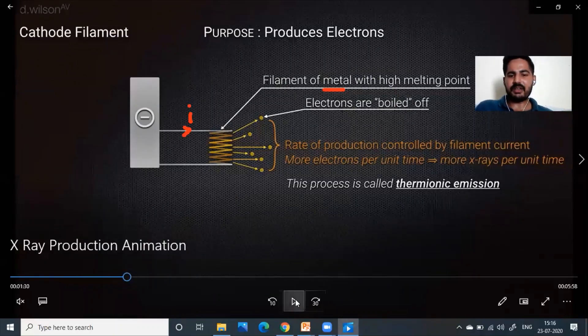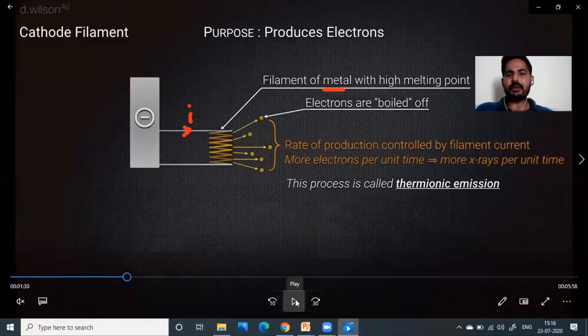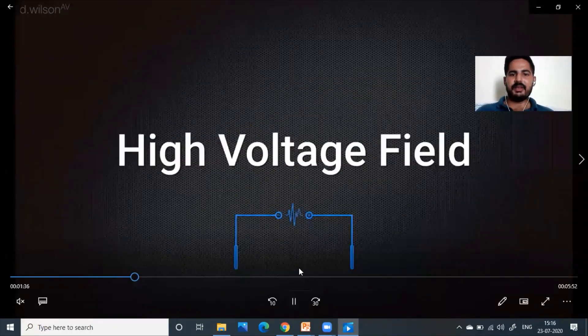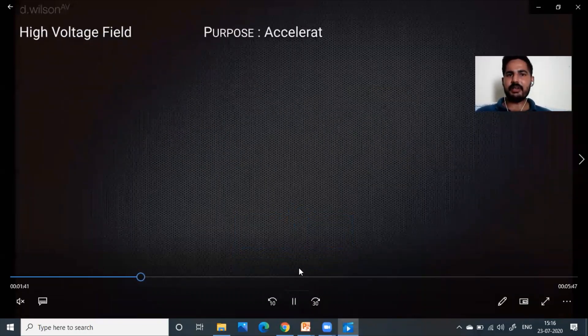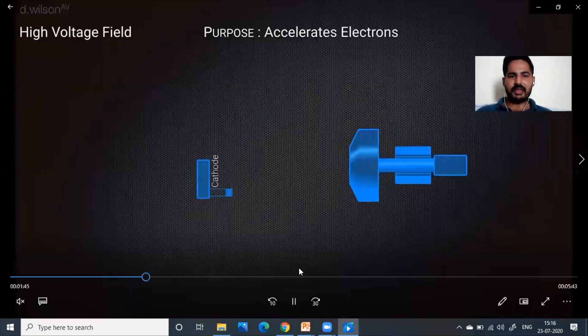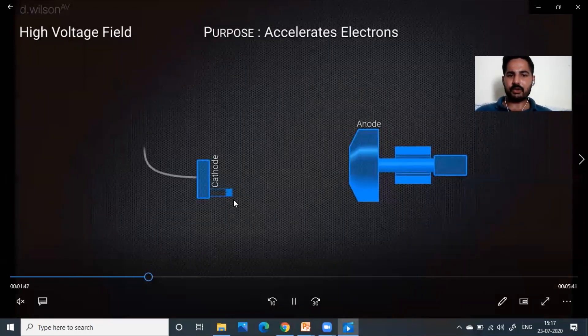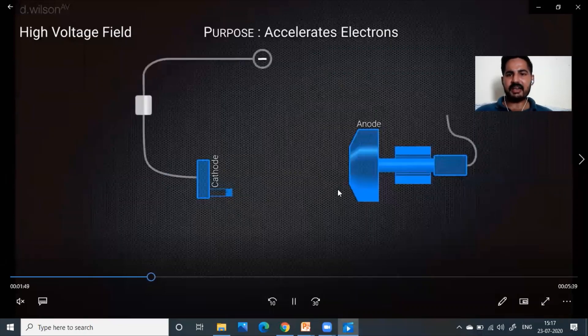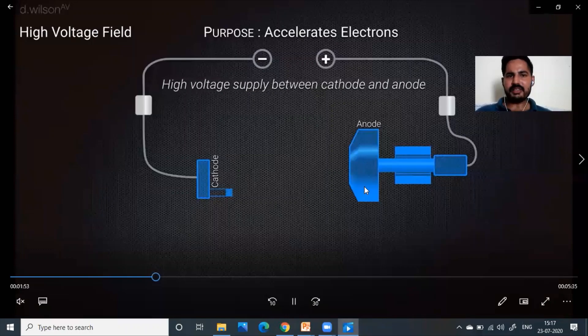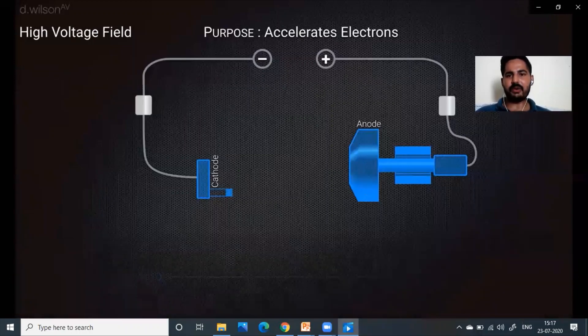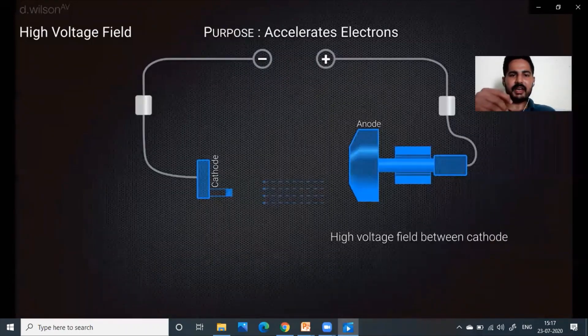Current is the factor which changes the number of electrons and the number of x-rays. Next, let's study the role of the high voltage electric field provided to this x-ray generator setup. Electrons are generated at the cathode, and at the anode there is a heavy metal where they are going to hit. High voltage is applied with positive to the anode and negative to the cathode.